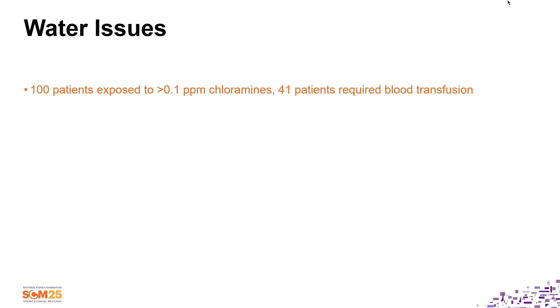Okay, this is what happened when 100 patients were exposed to greater than 0.1 parts per million chloramines. 41 patients required blood transfusion. RO system demand increased, and their GAC was not upgraded. And obviously, in this facility, the testing every 4 hours was somewhat ignored, and the result was a breakthrough of the carbon, resulting in hemolysis in the patients with a reduction of their hemoglobin. And 41 patients required blood transfusion. So if your facility is expanding and the demand for water is expanding, make sure that the design actually includes the calculation for your carbon size. Carbon size is very critical. Okay.